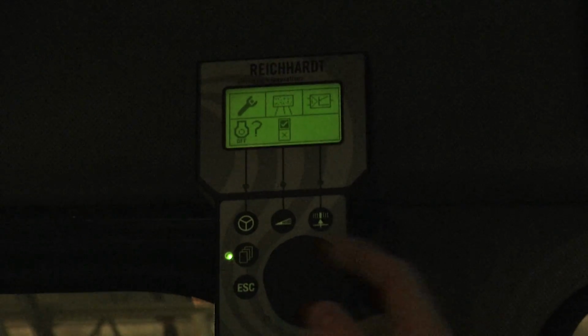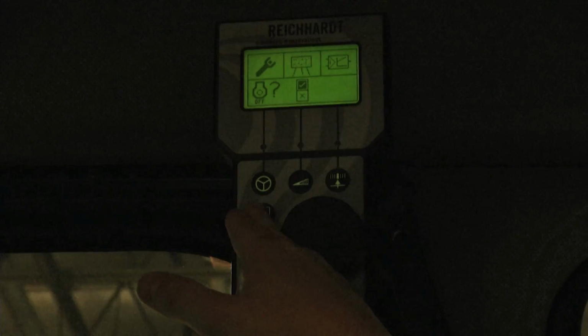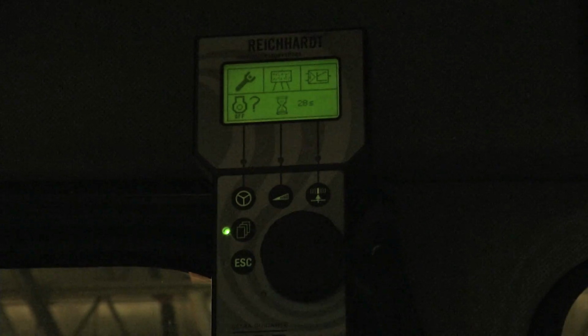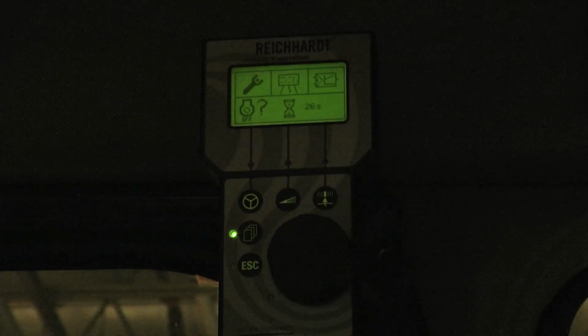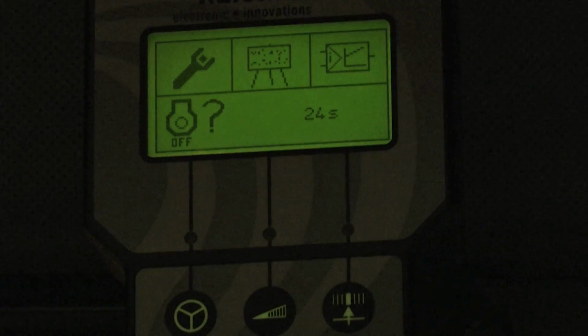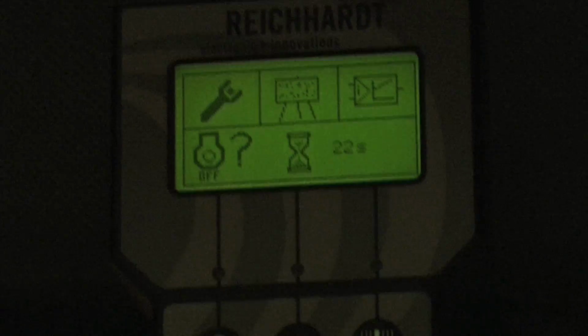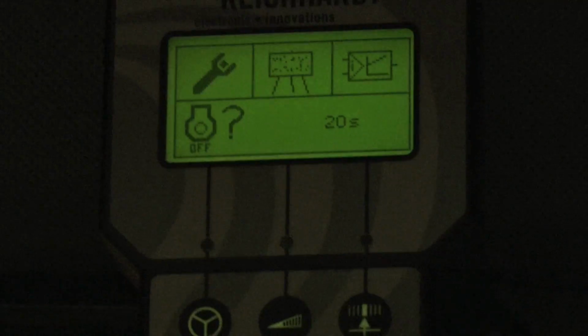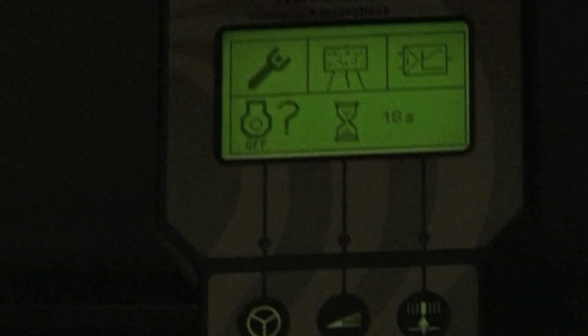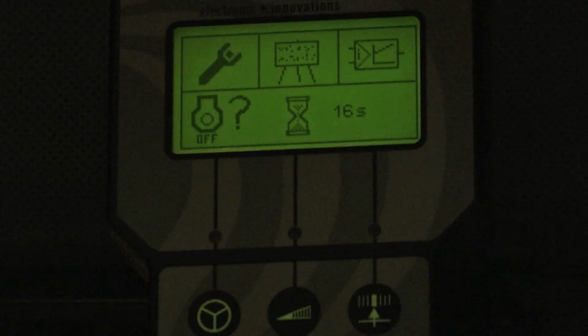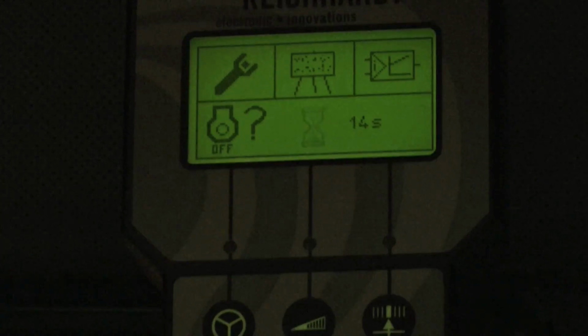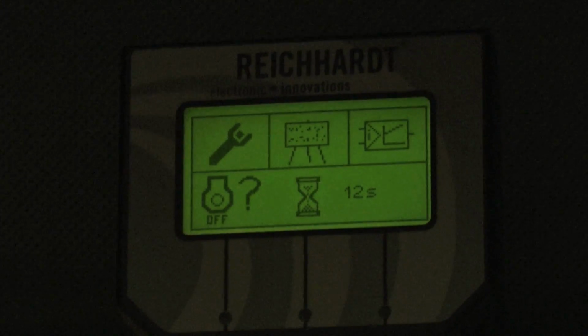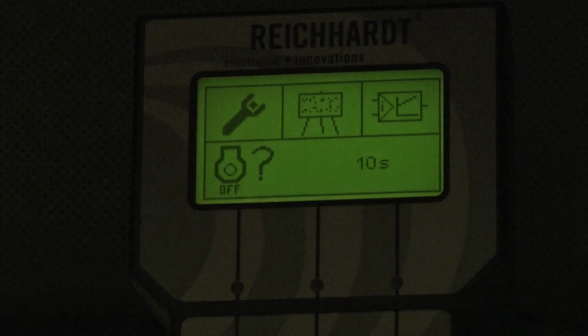You highlight the checkbox, you hold the 3-page button or the wheel, and it starts counting down from 30. What this is doing right now is sending current to all the valve connection points and measuring the load. It takes 30 seconds, and at that point it immediately takes you back to the previous menu, and all the stored calibration values are now memorized and stored in the controller.